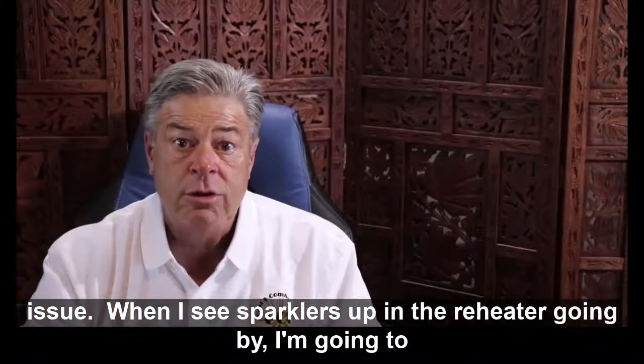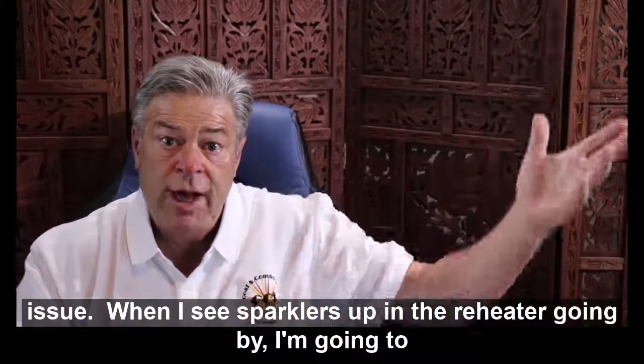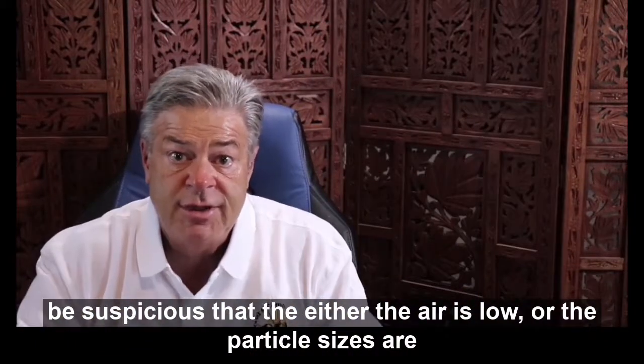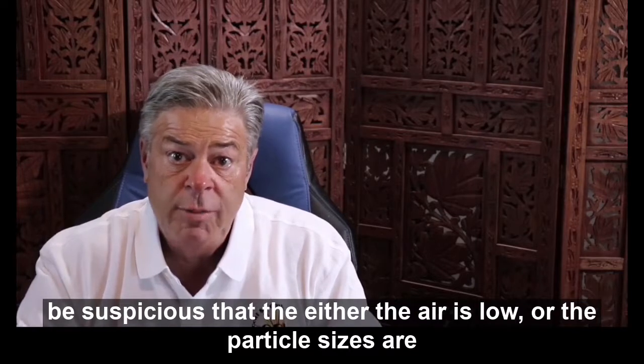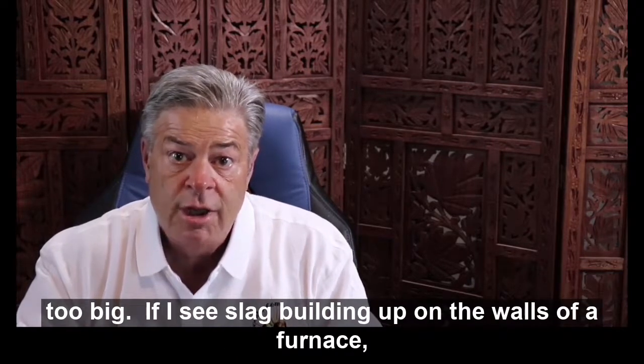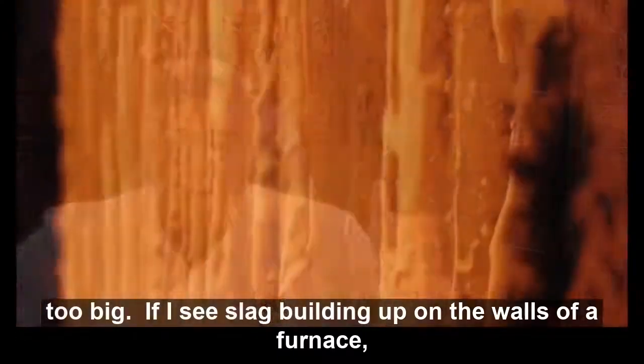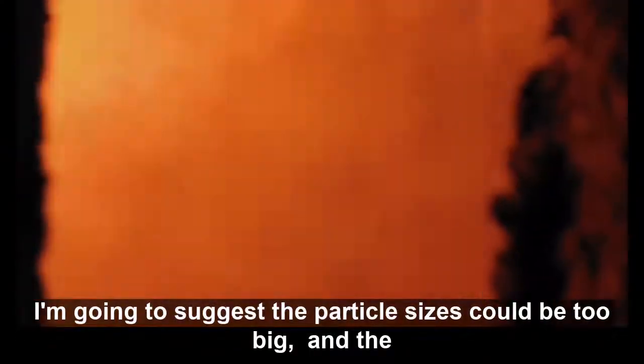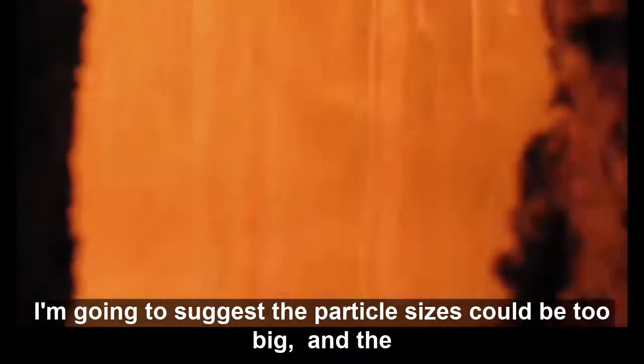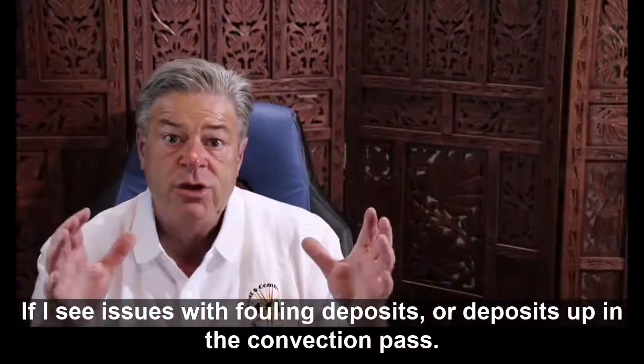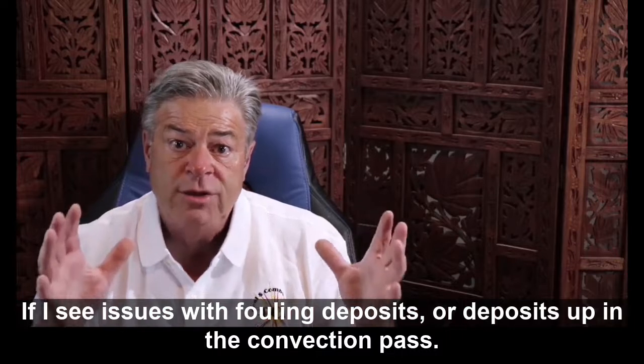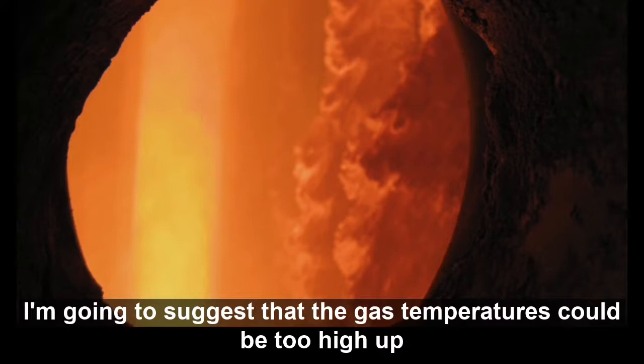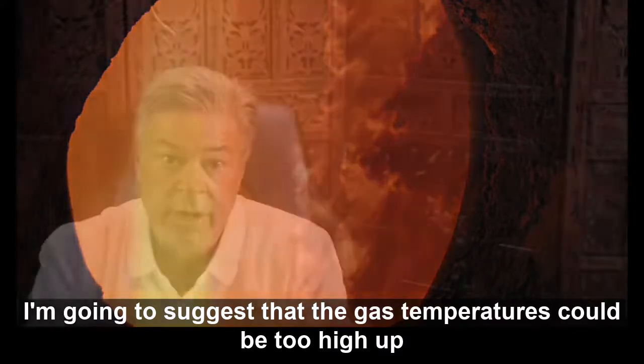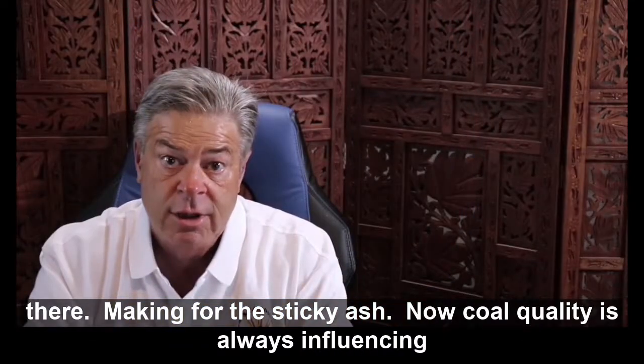When I see sparklers up in the reheater going by, I'm going to be suspicious that either the air is low or the particle sizes are too big. If I see slag building up on the walls of a furnace, I'm going to suggest the particle sizes could be too big and the primary airflow perhaps too high. If I see issues with fouling deposits or deposits up in the convection pass, I'm going to suggest that the gas temperatures could be too high up there, making for sticky ash.